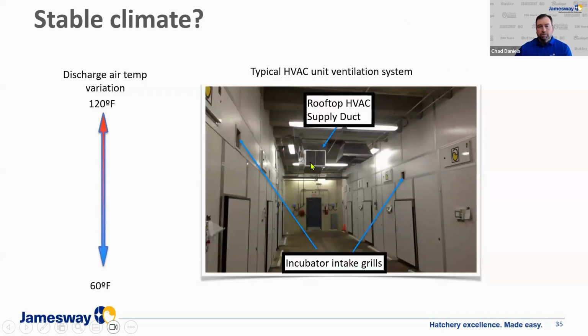So when we look at a system like this, an HVAC unit, typically they only have a couple of stages of cooling and a couple of stages of heating. And as a byproduct of that, you'll notice that these units have the capability of having a large discharge air temp variation. At times will be as low as 60 and maybe as high as 120 degrees. And that discharge air then coming into the room can be very inconsistent. And that's what gets consumed by the incubation equipment and causes that inconsistent environment in the incubation.